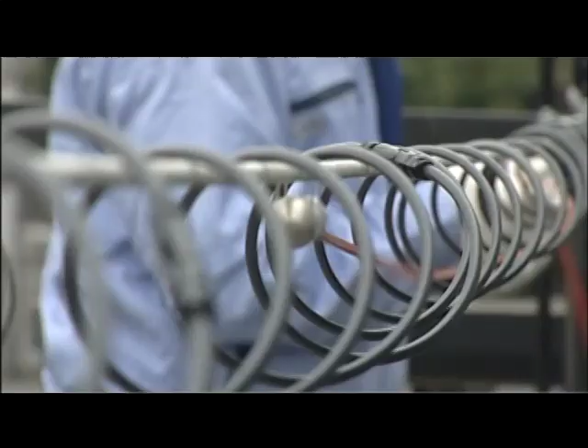When the installation tool reaches the next power pole, remove the shuttle runner and attach the installation tool to the cable towing rope. By pulling the installation tool back to the first power pole, the cable towing rope is placed within the Spiral Hanger.